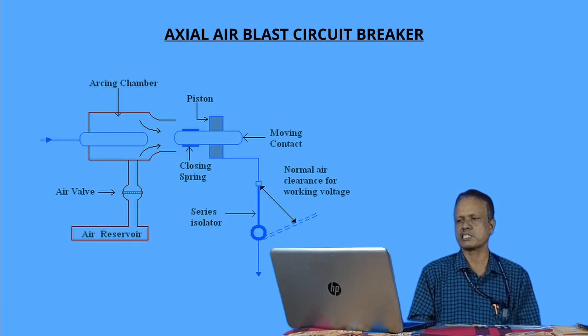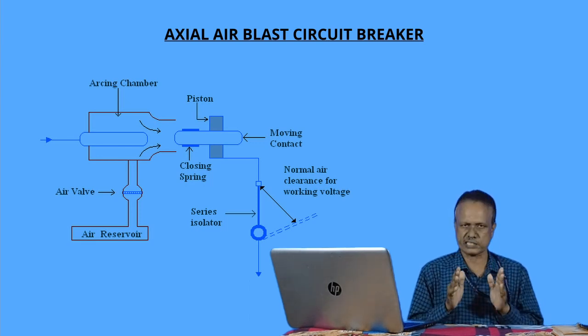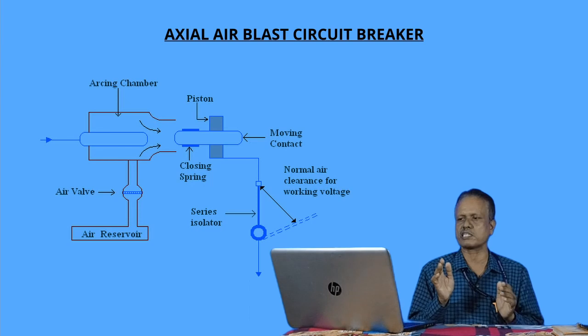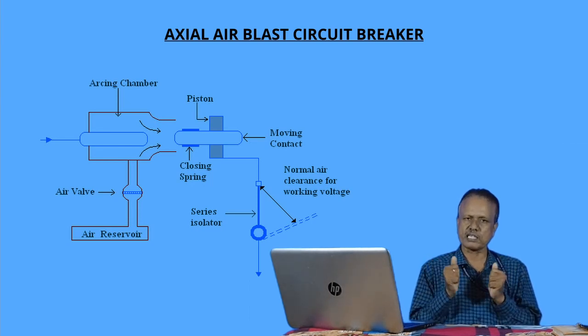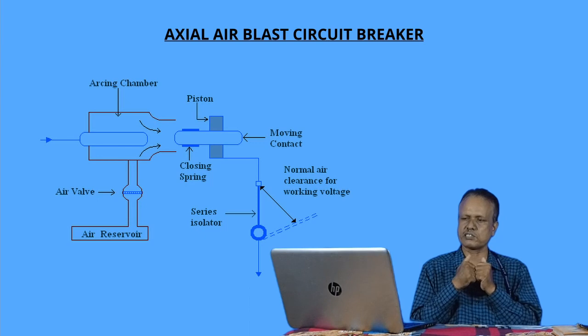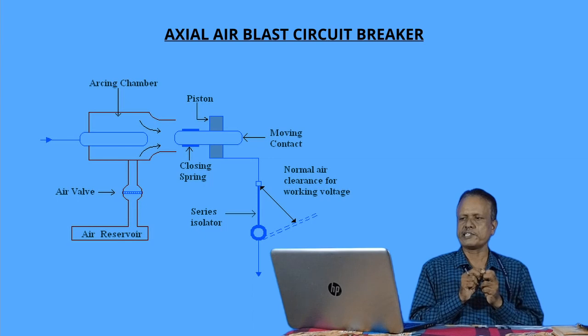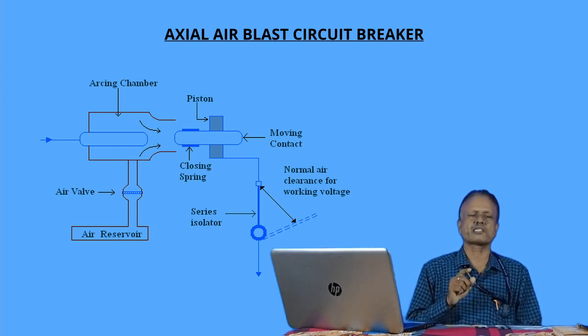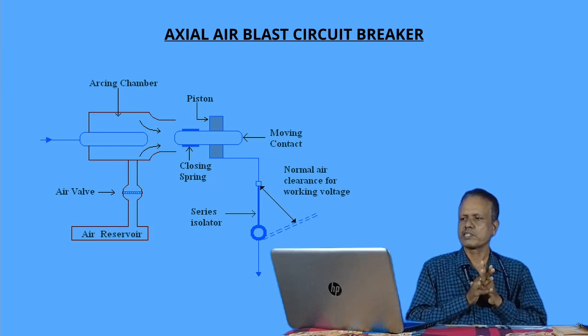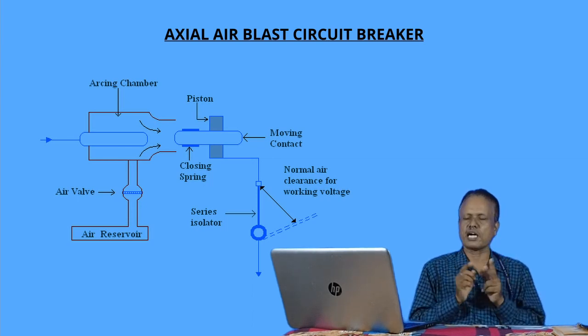Next, we will go to the axial blast type air blast circuit breaker. In this type of circuit breaker, two types of current carrying contacts are there, that is fixed contact and moving contact, which under normal condition are placed against each other with spring pressure, that is in close contact with each other, and the arcing chamber is connected with the air reservoir through an air valve. Similarly, this type of circuit breaker has a series isolator switch for sufficient clearance after the arc extinction for normal voltage.